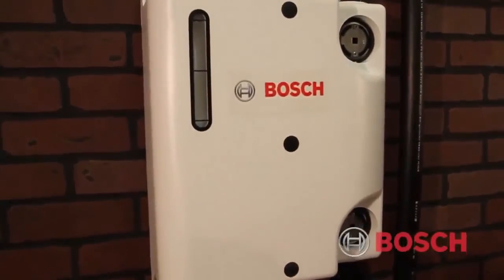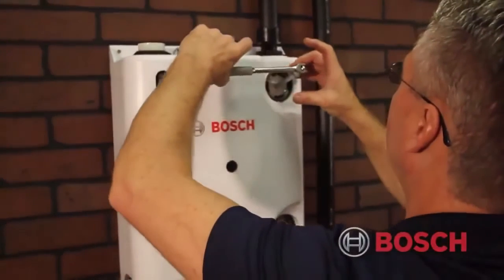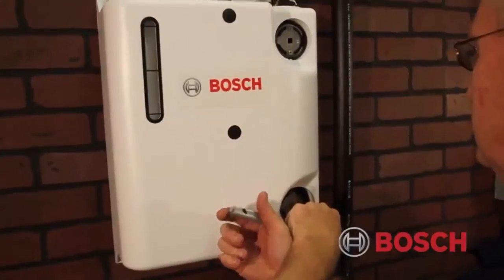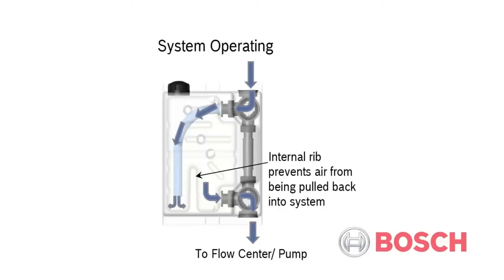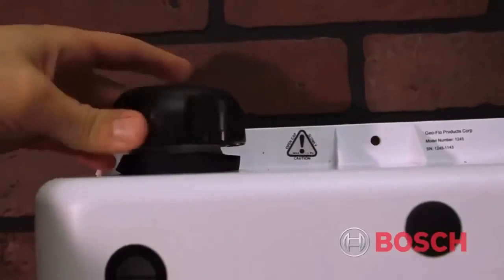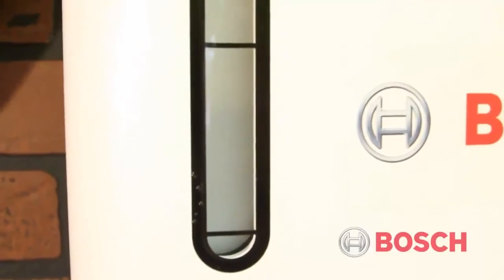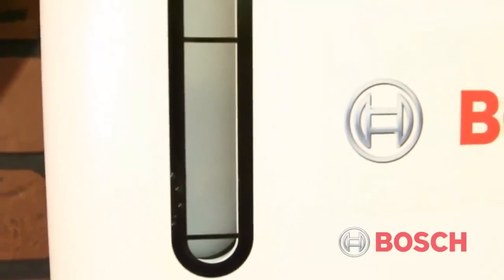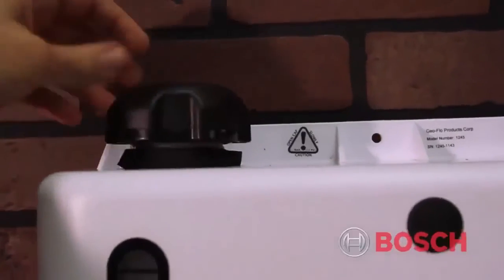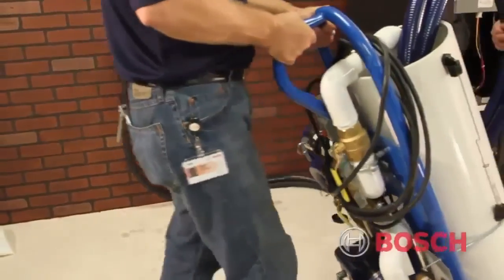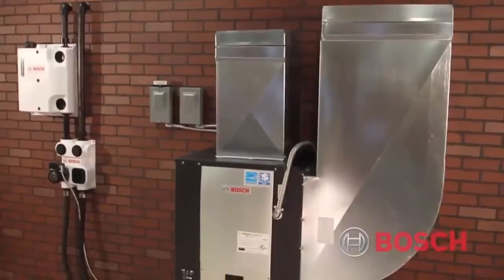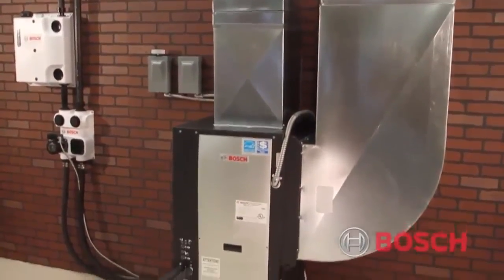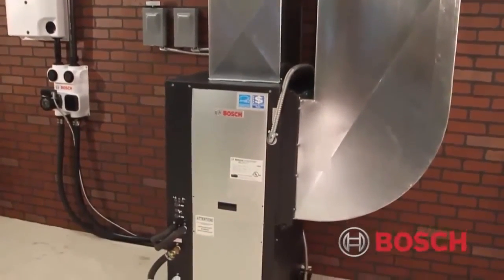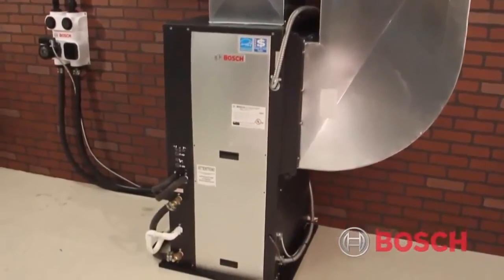Next, we're going to fill the GeoPrime 2.5 gallon reservoir. Rotate the GeoPrime tank three-way valves to the operation position. To fill, simply remove the reservoir cap and add water. Using the sight gauge, fill up to the halfway mark and then replace the cap until it clicks. The GeoLoop is now completely flushed of air and debris and the unit is now ready for startup commissioning. It's recommended at this point to remove and clean the flush cart screen filter.